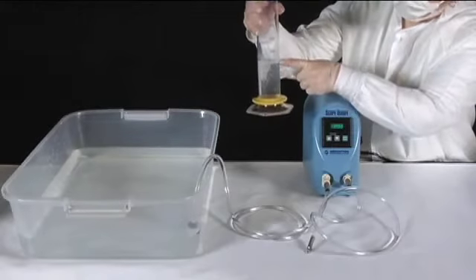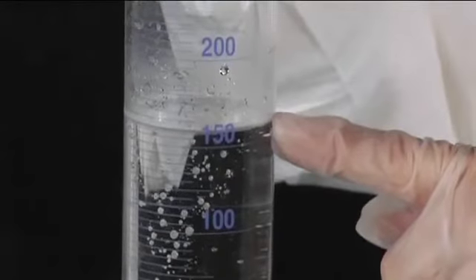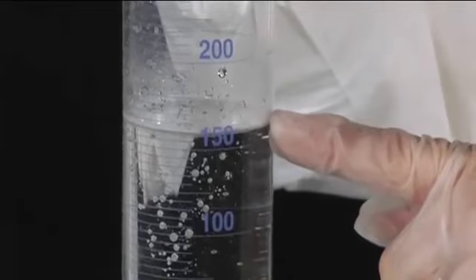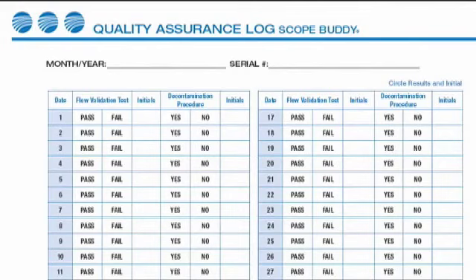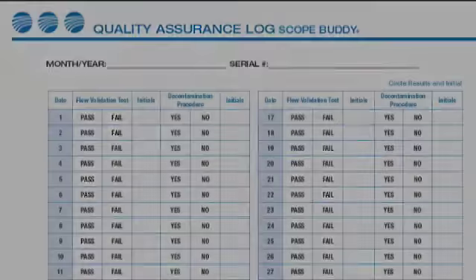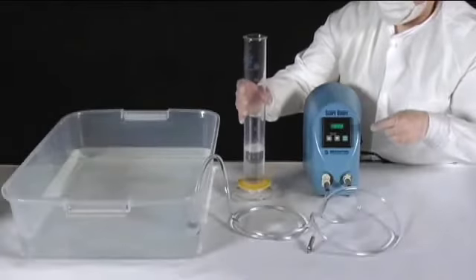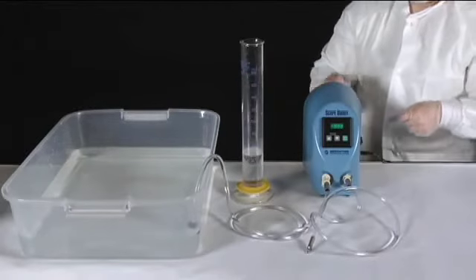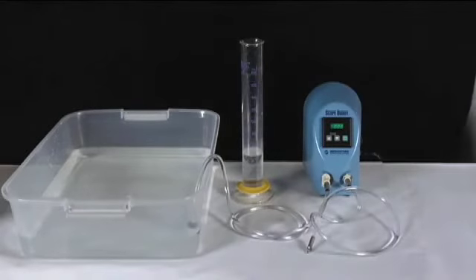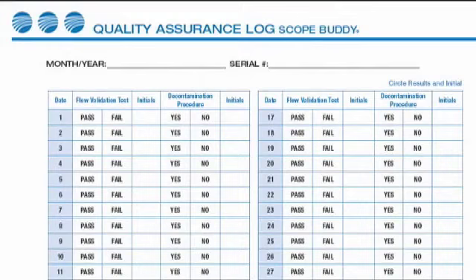If the dispensed volume is above 100 milliliters, then Scope Buddy is ready to be used throughout the day. Record a pass result on the Scope Buddy quality assurance log. If the dispensed volume is below 100 milliliters, do not use Scope Buddy and contact Medivators at 1-800-444-4729. Insufficient flow volumes can result in endoscopes which are not adequately flushed with the required amount of detergent or rinse water. Record a fail result on the Scope Buddy quality assurance log.